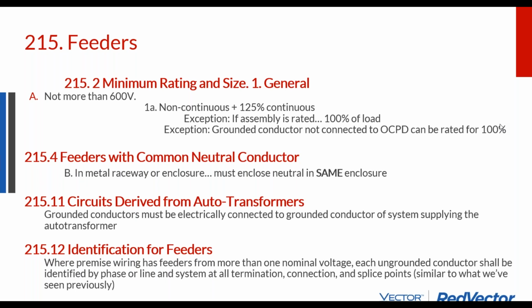Feeders with a neutral, the neutral needs to be run in the same raceway as the conductors. Circuits derived from autotransformers need to be connected to the grounded conductor of the system. We're going to talk about that in a minute. Identification of feeders. So when the premises wiring has feeders from more than one nominal voltage, each ungrounded conductor shall be identified by phase, line, and system at all termination, connection, and splice points. That's saying that your conductors need to indicate that they're positive and negative and at what voltage. Basically these become sticker requirements in the solar specific questions.